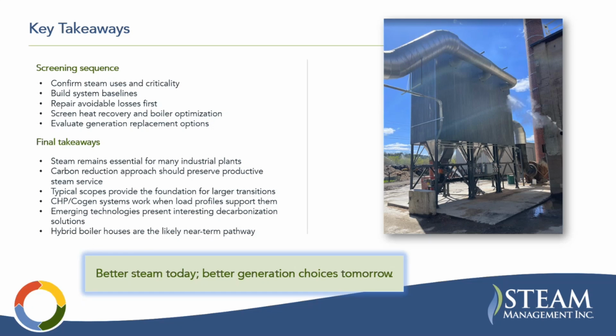But steam meters are always good. I would say steam meters and gas meters are it if you were only going to do two. And then usually you have a makeup water meter just on your makeup water supply. But that's either measuring makeup water and condensate or both. So steam output, condensate return, makeup water flow, and fuel, I would say, are probably the highest priorities, generally speaking. But yeah, that's kind of a case by case basis.